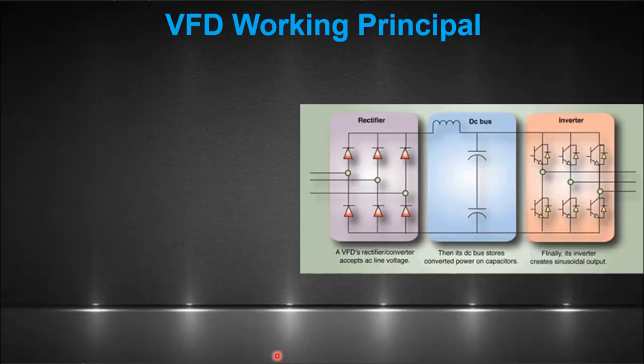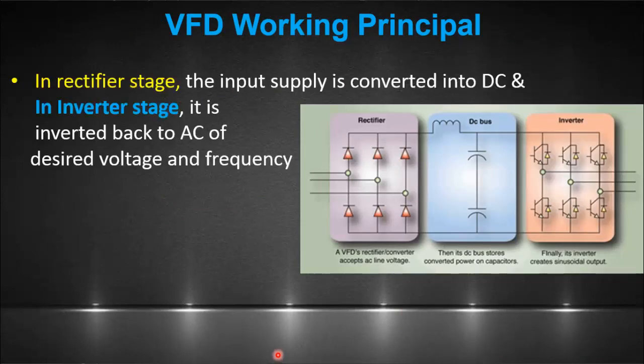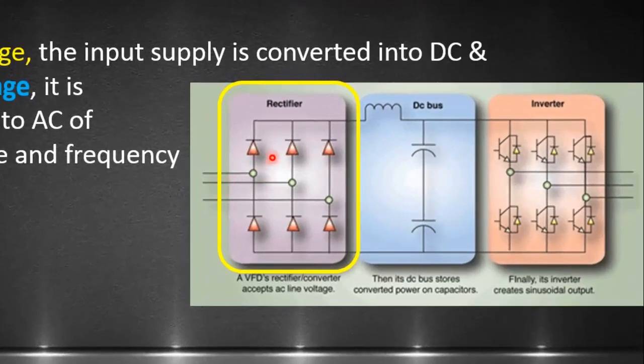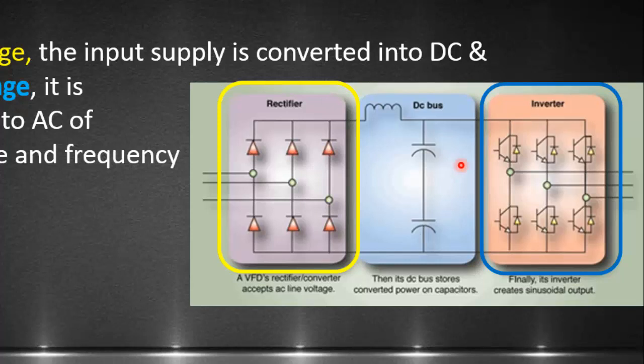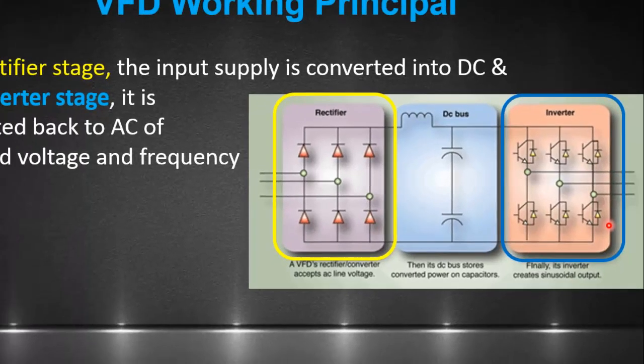VFDs control the motor by varying both frequency and voltage of the input supply at the same time. In a VFD, the first stage is the rectifier stage, where three-phase AC voltage is converted into DC using thyristors. The second stage is the DC bus, which uses a capacitor bank to filter the rectified DC. The final stage is the inverter stage, which uses six IGBTs to invert from DC to a three-phase AC signal, but now with variable voltage and frequency.